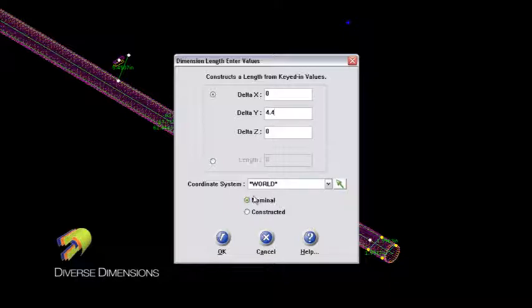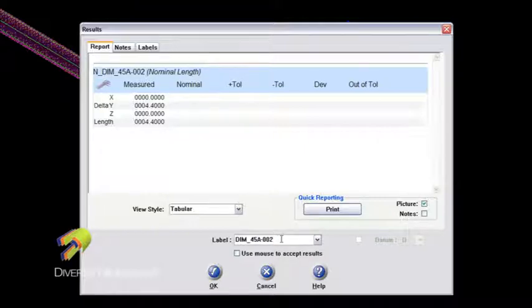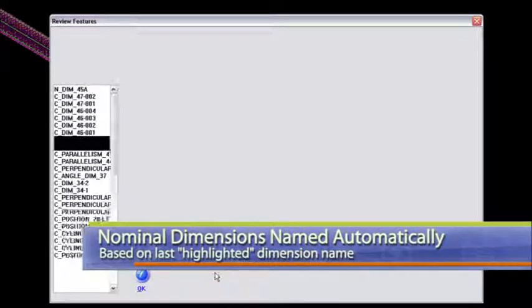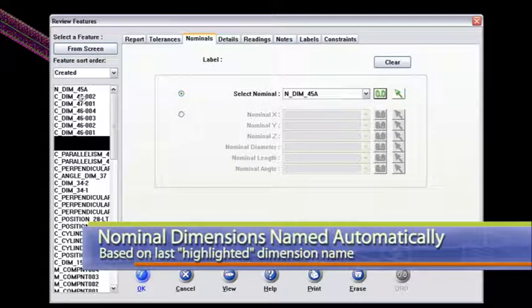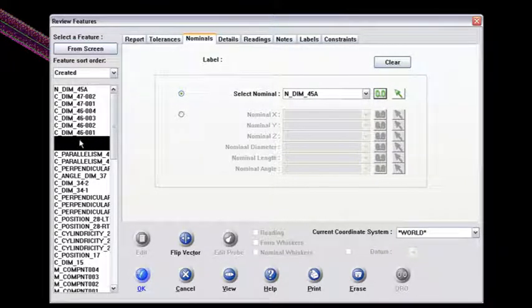Faro assumes it's going to be a nominal, which is great, and it's putting it into the coordinate system of the world — the coordinate system I'm measuring in — so I'm okay with that. Now look what it does here: it develops this nominal dimension 45A, calling it 002. I'm just going to get rid of that 002 and say okay. Notice what it's done here in review features — it's constructed this nominal dimension 45A and is associating that nominal dimension to the two measured dimensions I have highlighted. I've got both of those highlighted.